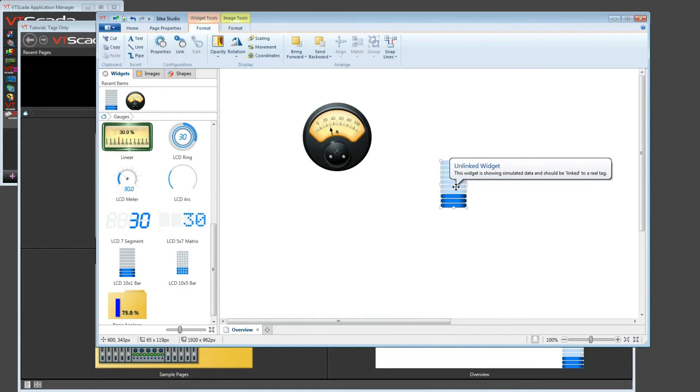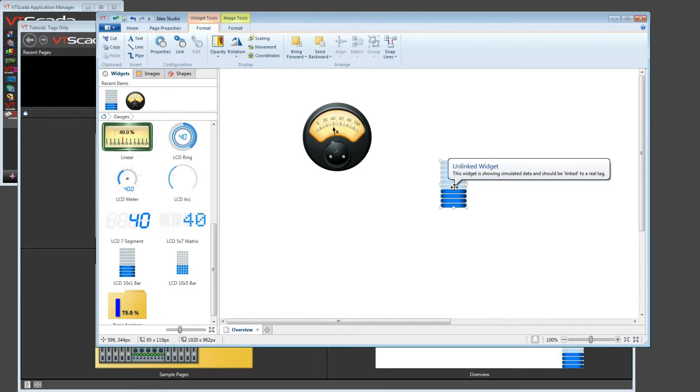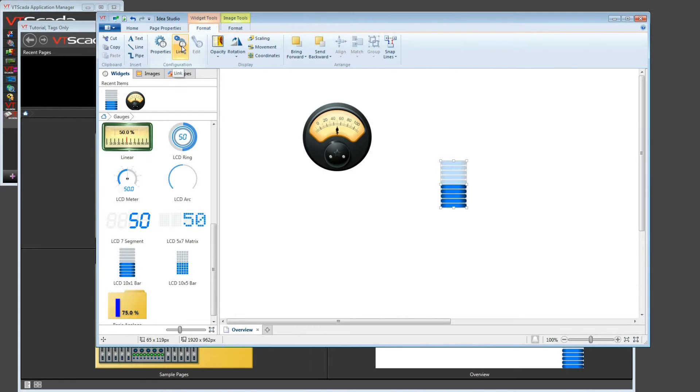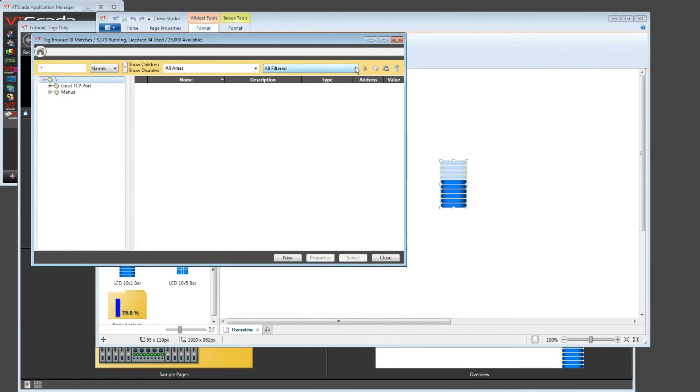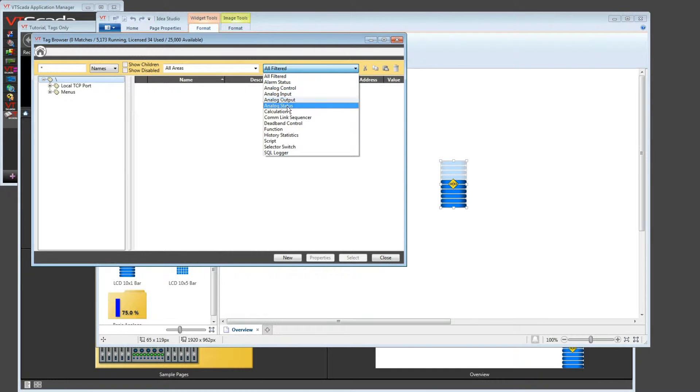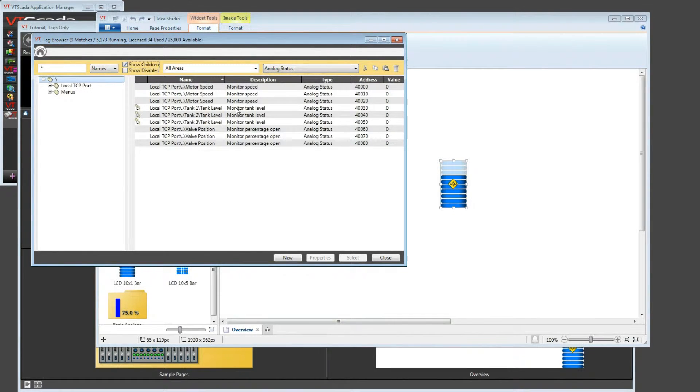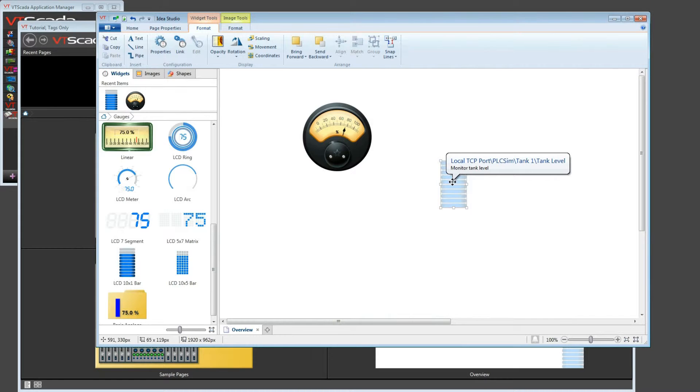You'll notice that, at the moment, I've got unlinked widgets here. This yellow indicator is telling me that currently nothing is linked. Very important to link every widget that you draw. So the way to do that is to select a widget and then go up to the link button. And this allows you to choose the tag that you want to be represented by that widget. That opened the tag browser. And I'm going to look for my analog status tags, all of them. And here I can choose, perhaps this is going to represent a tank level. Choose the tag that I want. Click the select button. And now this widget is going to represent the values from the tank 1 tank level.